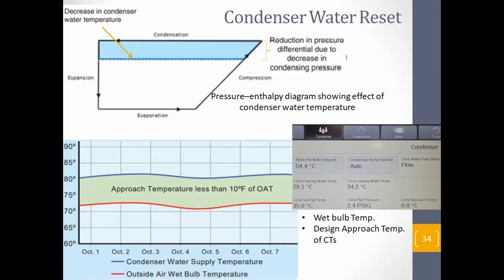In this particular facility, they have fixed the condenser water leaving the cooling tower at a particular temperature. But in modern days, we don't need to fix it like that. We can have a wet bulb temperature sensor, add an approach temperature, maybe 3 degrees on top of that, and make that the condenser water leaving temperature. That will make things more dynamic.